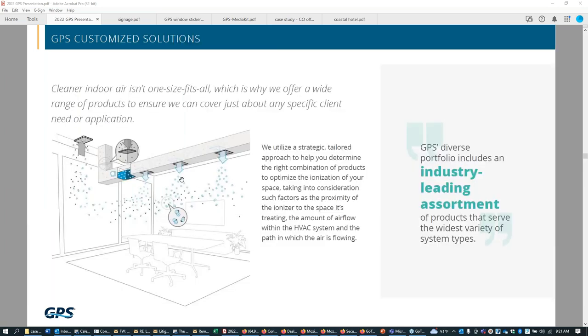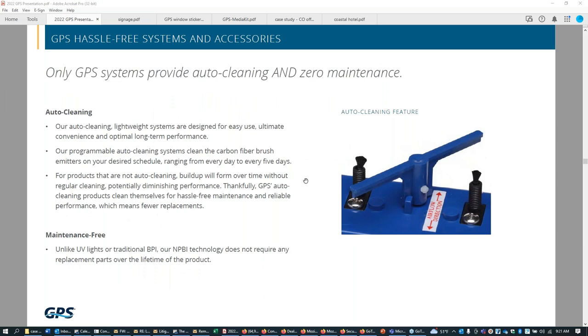So this schematic shows a duct mounted application where the ions are being introduced into airflow and then being delivered to the space through the supply air diffusers. This is an example of one of our auto cleaning devices. Our duct mounted products and our fan mounted products have this feature where every day this wiper blade will actuate and rotate to remove any dust or lint that accumulates on the positive or negative fiber bundles. And I mentioned that this technology is called needle point, but it's not a needle. These are actually thousands of carbon fiber bristles that emit the positive and the negative ions.